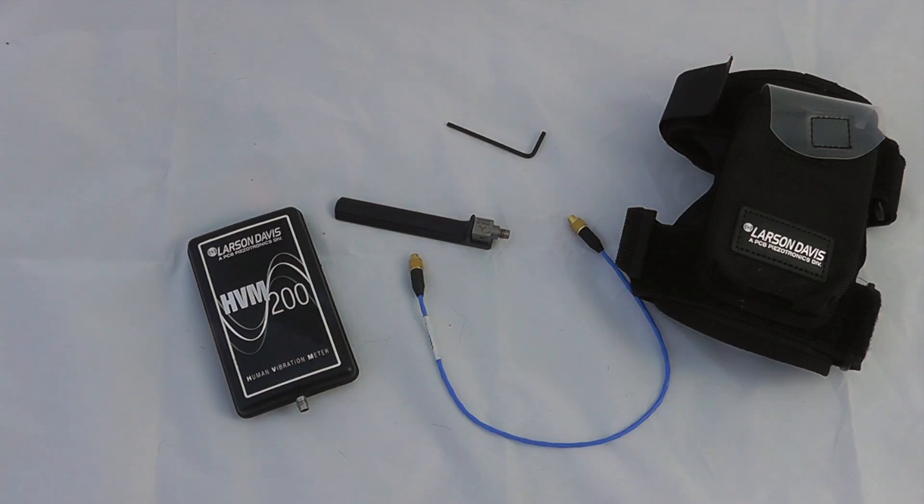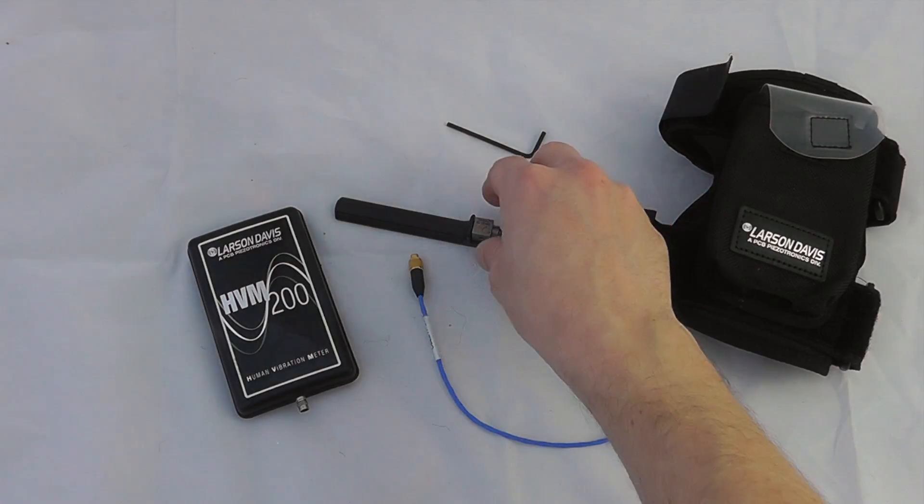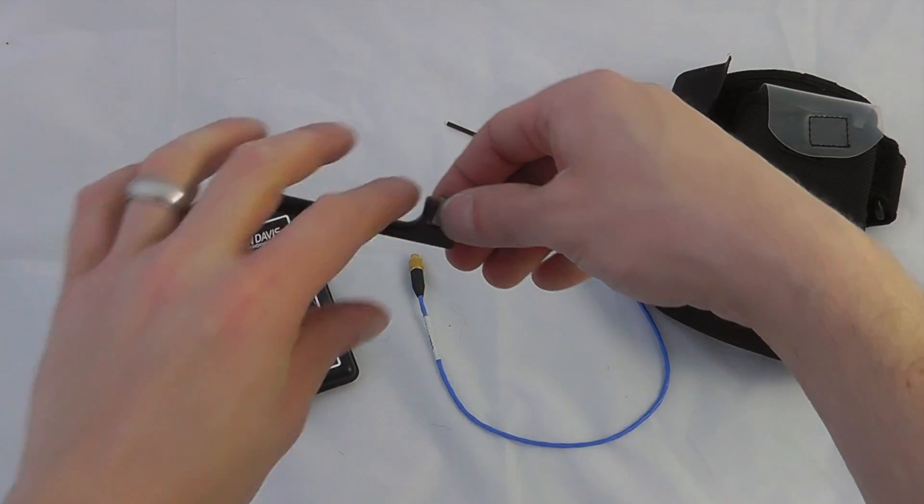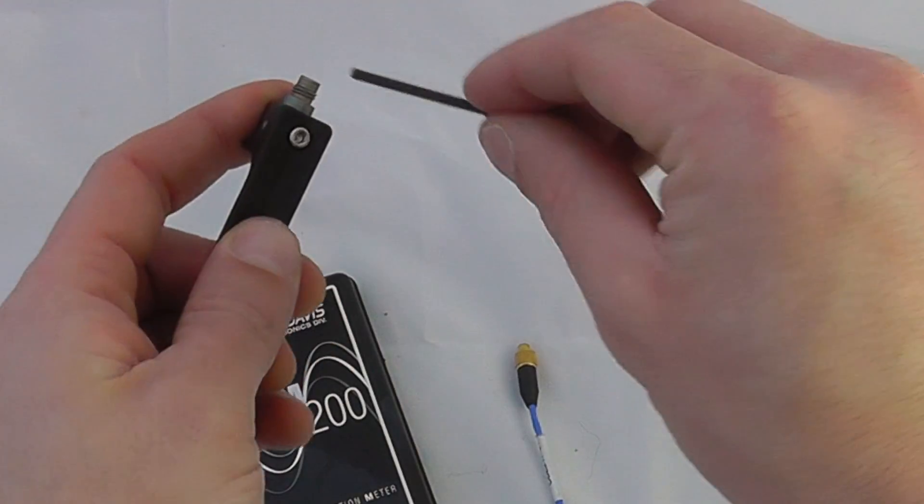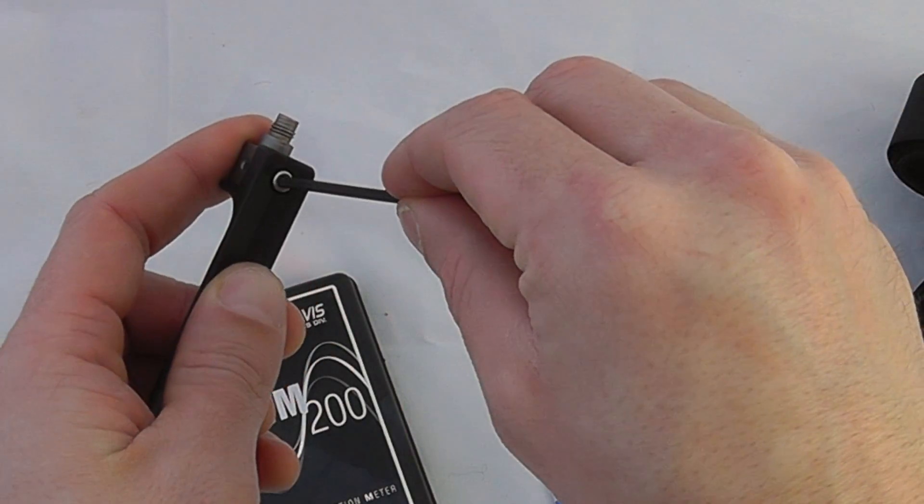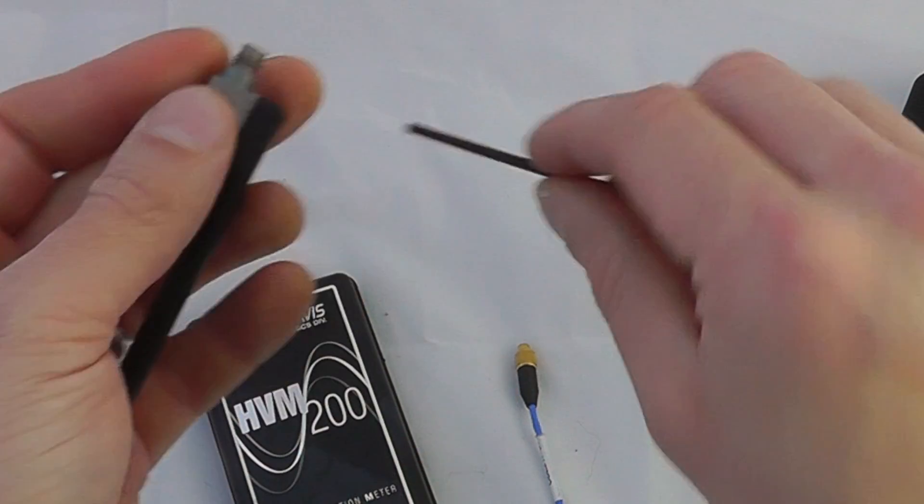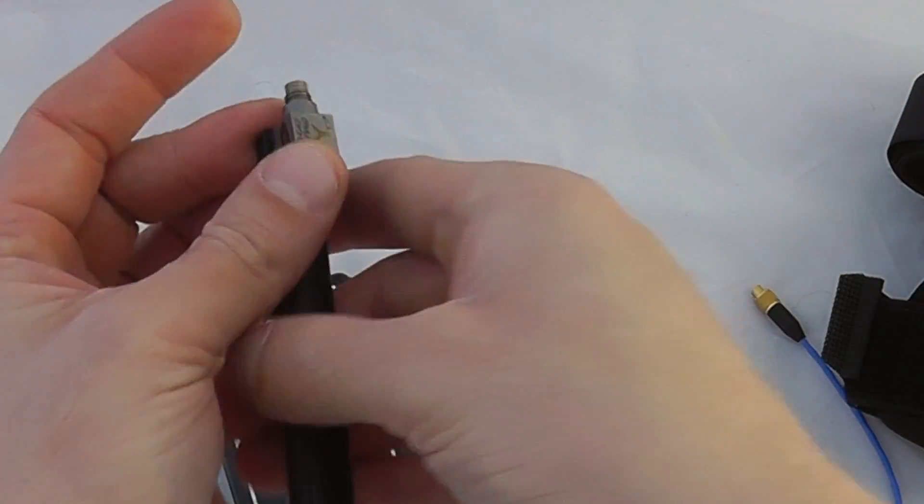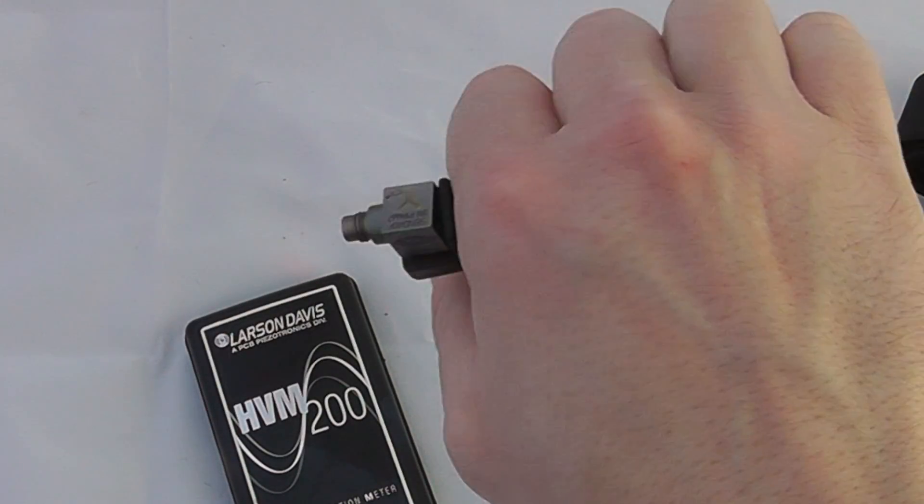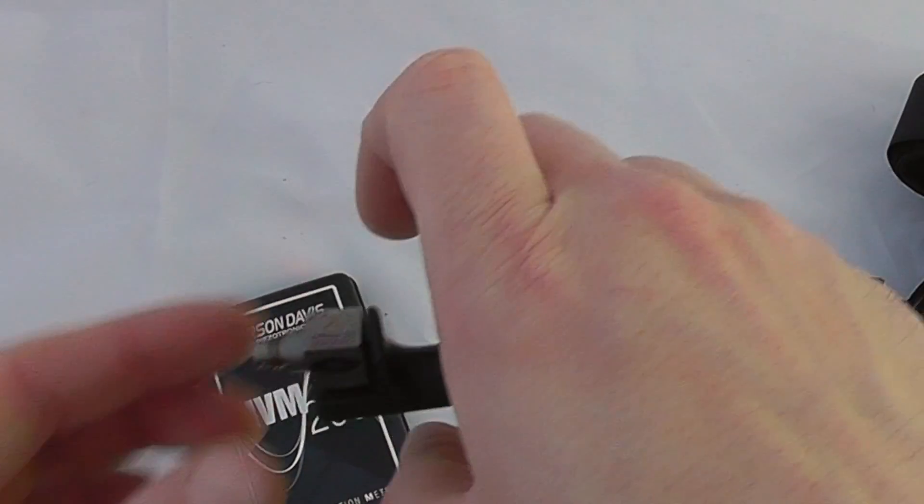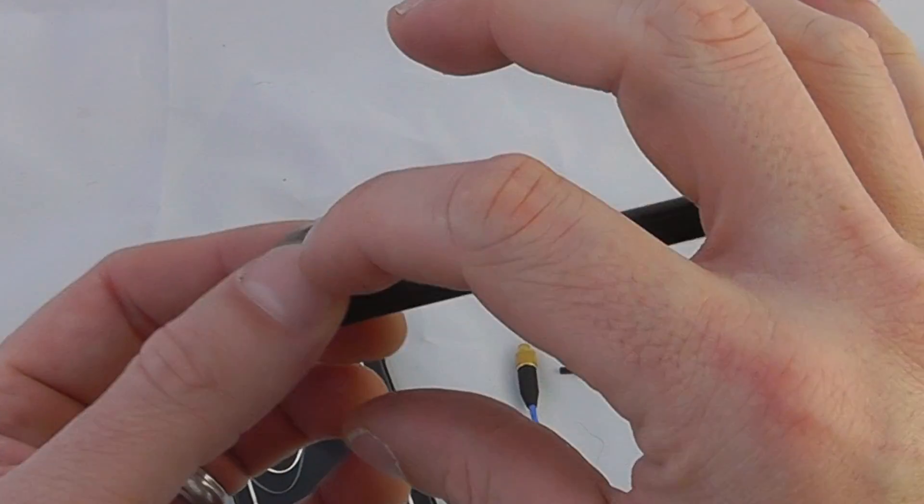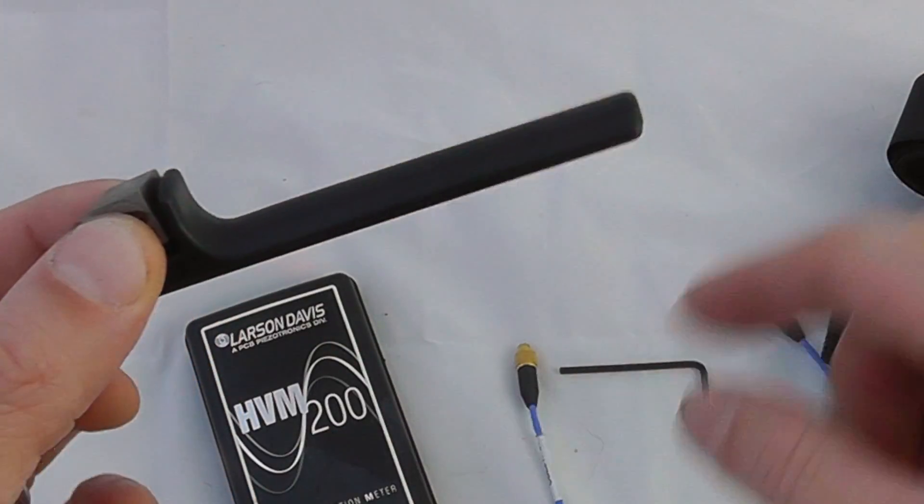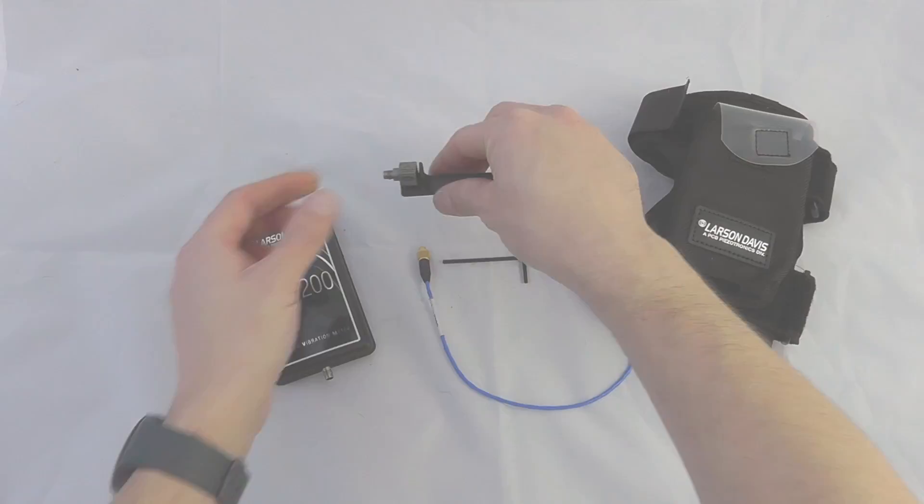In this particular instance we're using a hand arm accelerometer. We have attached this using an allen key and screw onto a standard handle mounting block. I would normally suggest using a standardized mounting block where we can jubilee clip onto the tool.